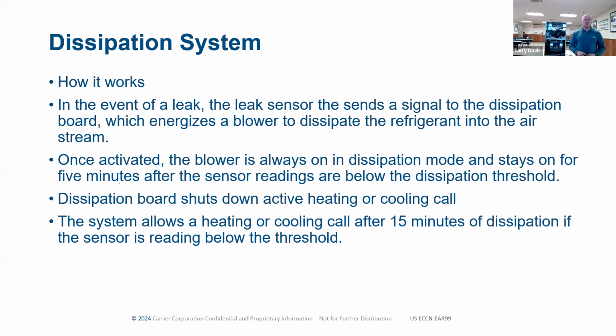I know they've tested this similar scenario at the lab. In fact, in some of the slides we'll see, they're hooked up to an 80% furnace. The key there is monitoring that. What I would suggest, if you wanted to be double safe about it, is add a second dissipation system. You'll see that available here later on as a third-party or aftermarket product. Add another one and sense it out in the closet if that's a concern. That way, if a line leaks in the closet, you'll sense it in the room, shut the furnace off, and run the blower. You're really not going to dissipate much because you're leaking into your closet, but it'll at least shut the blower down until that sensor says it's clear.